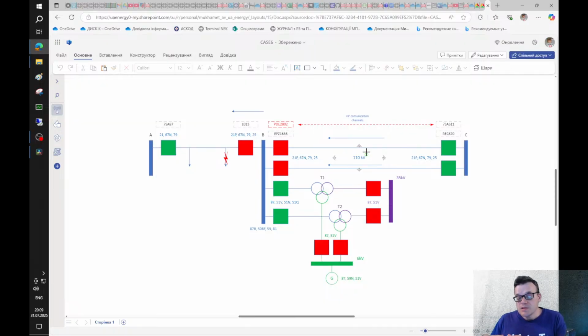I described that there were problems with settings, but the main reason for that event and such a long clearing time is, in my opinion, not good maintenance on this power plant B side. So after that event, I wrote a big report. We sent this report to the power plant. Usually, if there are some problems with any protection, we do after-fault maintenance or checking. So the staff from this power plant said that they checked. They don't say if they found something on their protection. So I can't say or describe what that was.